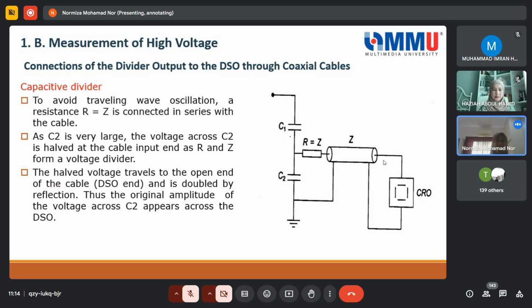So to avoid traveling wave oscillation for the capacitive divider, normally a resistance R equal to Z is connected in series with the cable. The capacitive divider cable is normally provided by the manufacturer, because in that cable they already consider this R equals to Z.